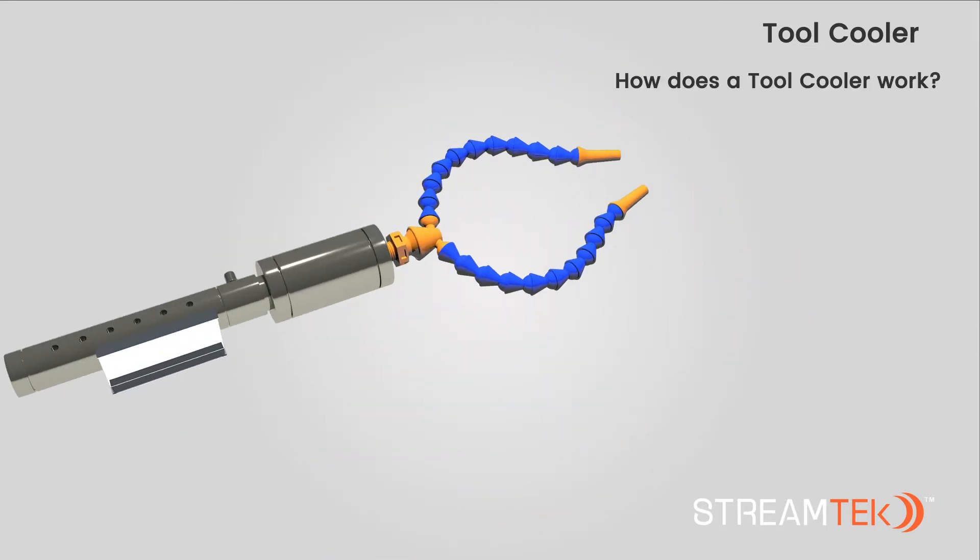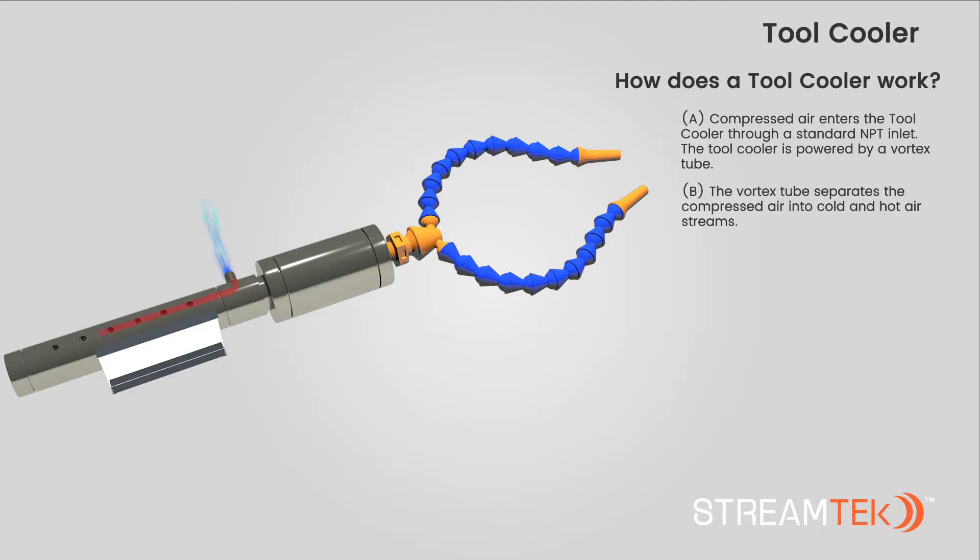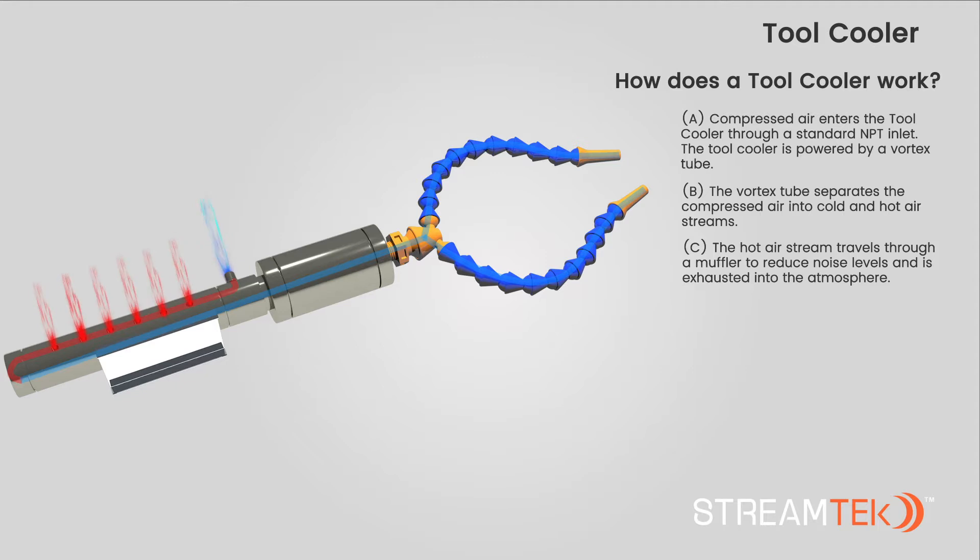How does a StreamTek tool cooler work? A. Compressed air enters the tool cooler through a standard NPT inlet. The tool cooler is powered by a vortex tube. B. The vortex tube separates the compressed air into cold and hot air streams. C. The hot air stream travels through a muffler to reduce noise levels and is exhausted into the atmosphere.